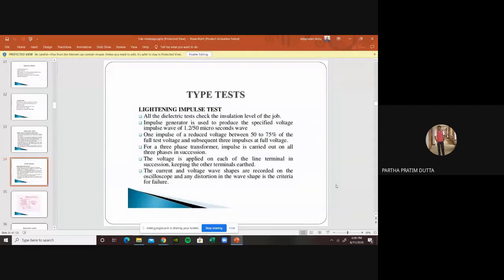In three-phase transformers, the impulse is carried out on all three phases in succession. We usually use a machine which chops the sine wave and amplifies it to some kV level, and that is applied separately in succession on each phase to see whether it can withstand it or not. The entire wave shapes, current and voltage, are observed on the oscilloscope.